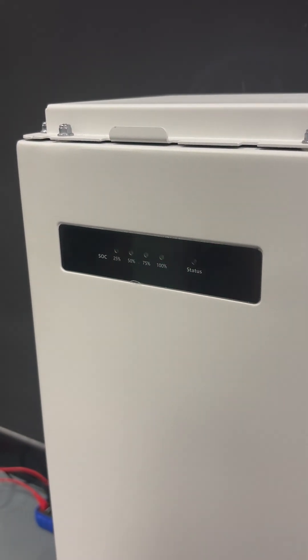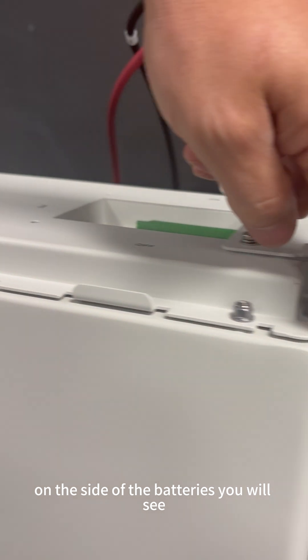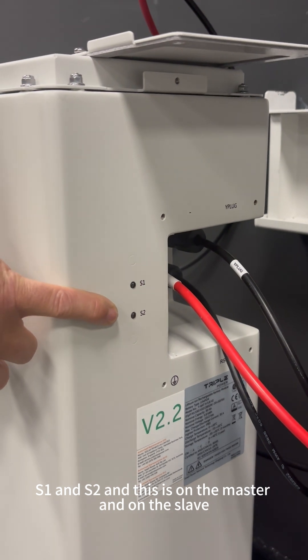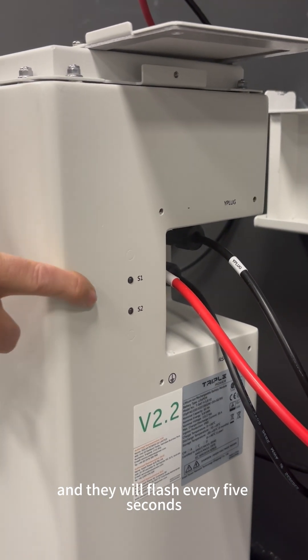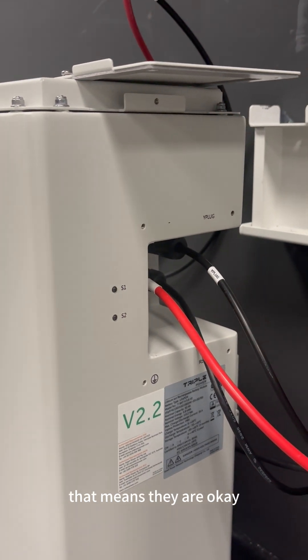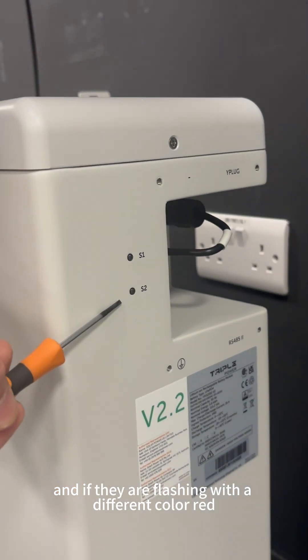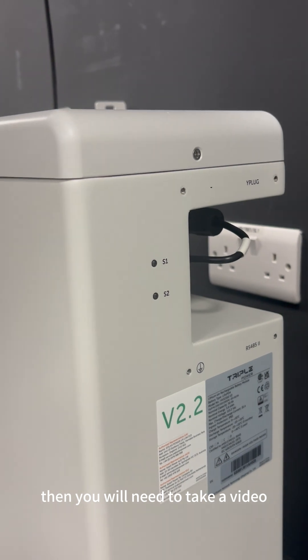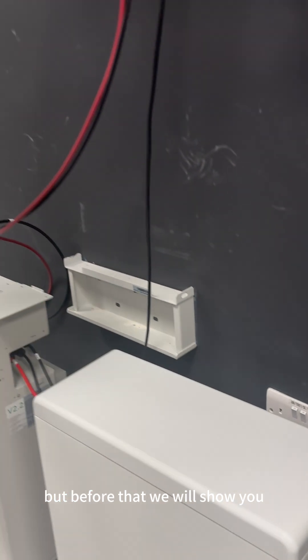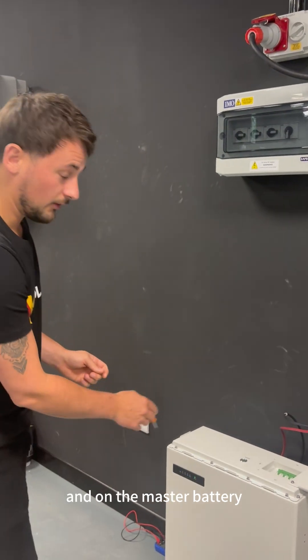Now you've seen that that's green on the side of the batteries. You will see S1 and S2 and this is on the master and on the slave and they will flash every five seconds. When they are both flashing green that means they are okay. If they are flashing with a different color, i.e. red, then you will need to take a video and get in touch with us. But before that, we will show you some tips on how to measure the voltage on the slave battery and on the master battery.